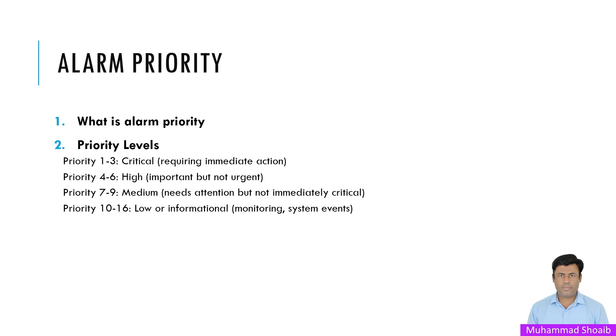Typically the scheme is: priority 1 to 3 is critical and requires immediate action or attention; priority 4 to 6 is high priority and important but not urgent; priority 7 to 9 is medium, needing attention but not immediately critical; and priority 10 to 16 is lower — informational, just for monitoring. For example, if our client wants only critical signals to appear on the alarm control screen, we can filter alarms with priority 1 to 3. We will see practically how this works.